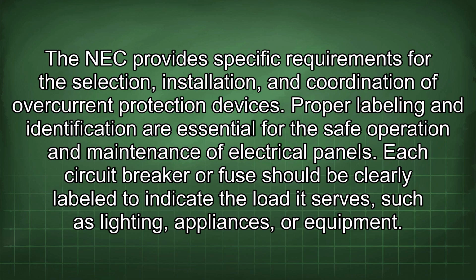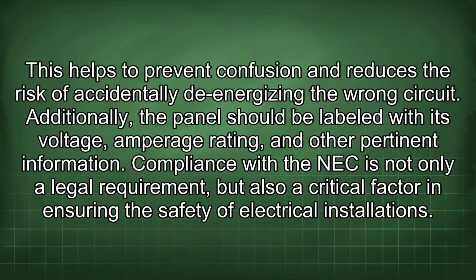Proper labeling and identification are essential for the safe operation and maintenance of electrical panels. Each circuit breaker or fuse should be clearly labeled to indicate the load it serves, such as lighting, appliances, or equipment. This helps to prevent confusion and reduces the risk of accidentally de-energizing the wrong circuit. Additionally, the panel should be labeled with its voltage, amperage rating, and other pertinent information.